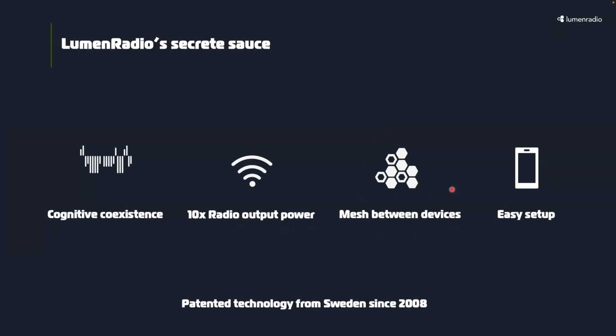Where you're bridging between different devices, if you have one wireless device next to each VAV, the VAVs are basically meshing with each other back to the Jace. That's exactly what we did in a skyscraper with 19 floors, where the node on the 17th floor was jumping back to floor 14, floor 11, floor 8, floor 5, floor 3, and then down to the basement. It's a very effective method to cover an entire building, which, for example, LoRa can't, because they are a star network that can't mesh really.